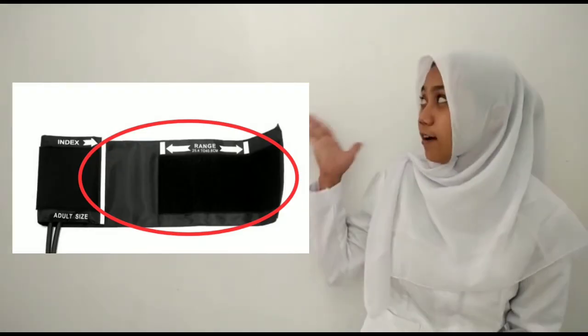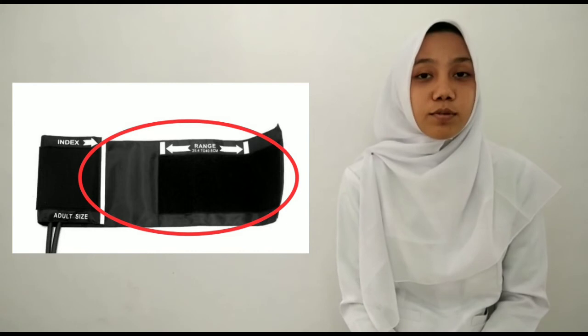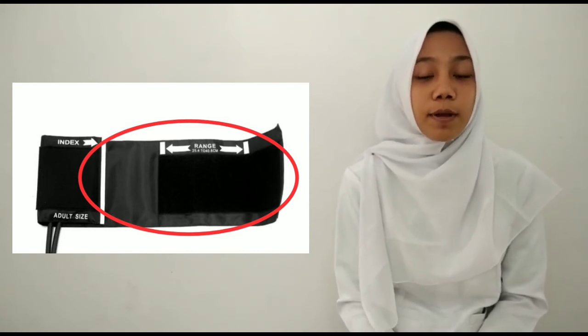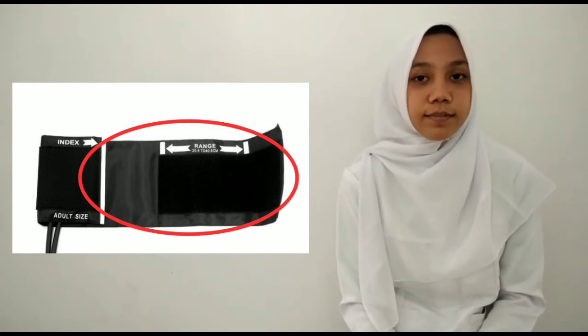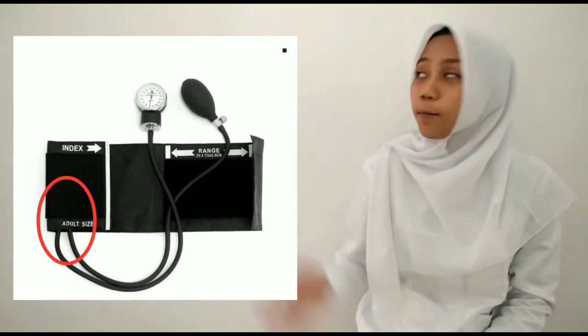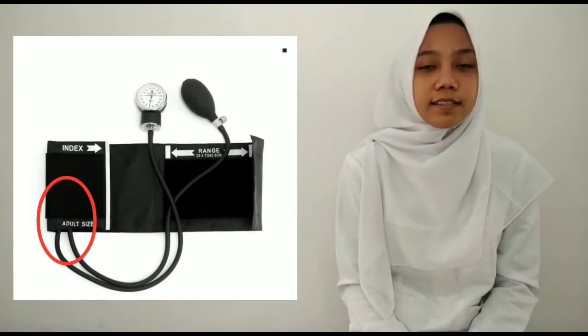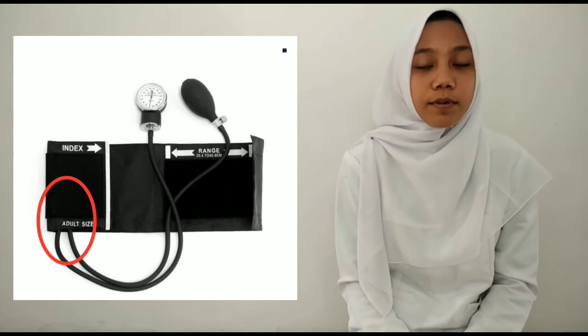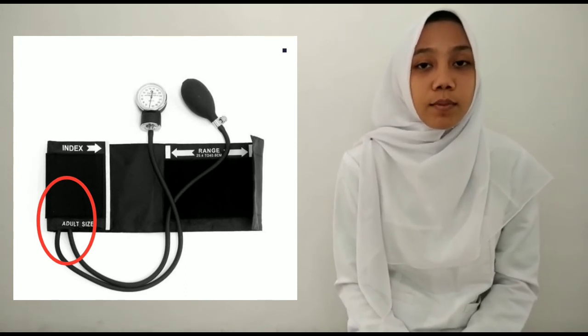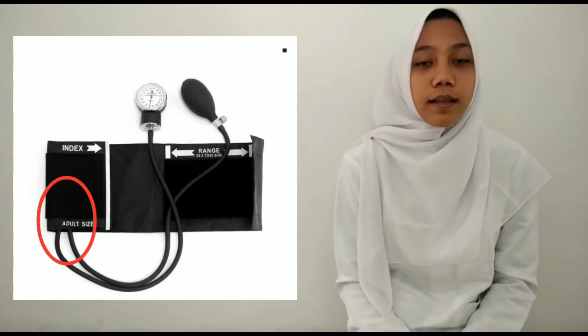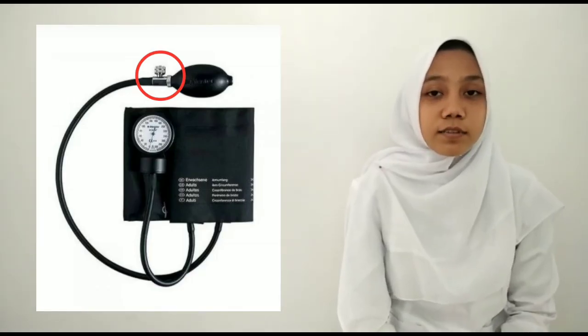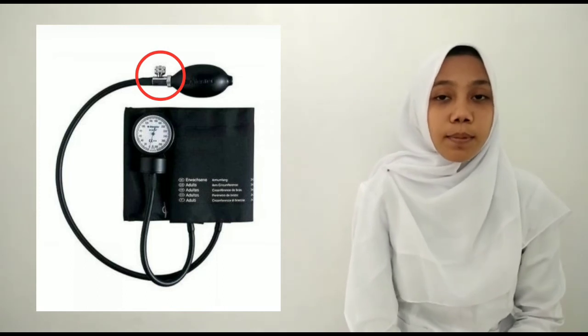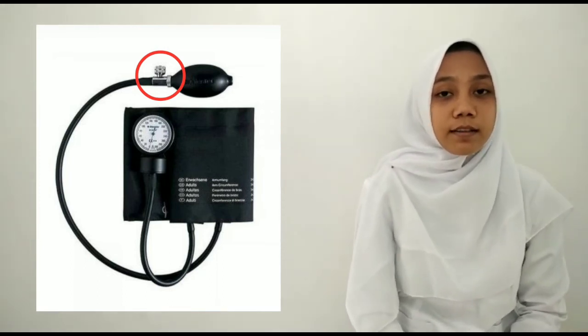The next part is the cuff, which serves to accommodate the air pressure and to detect the patient's blood pressure measurement. The next is the pressure bladder, which is an inflatable part filled with compressed air to close the artery. And the last is the valve, which serves to close or open the air flow from the pump into the cuff.